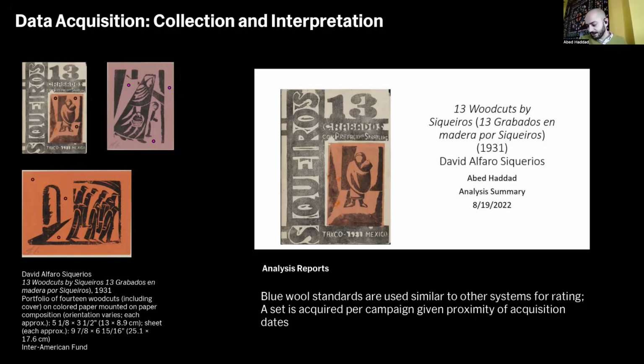And when we start our day of measurements, I usually turn on the LED light source. I let it warm for about 10 minutes or so before taking my blue wool replicates. We do 3 replicates per colorant. So that includes both the blue wools and the objects that you're looking at for 10 minutes. With the blue wools, we would let it run the entirety of the 10 minutes, but with an object, as I mentioned earlier, we do have a stopping point of JND 1.5 delta E 2000, just because we are trying to avoid making any kind of visible change to the object as we're analyzing it.